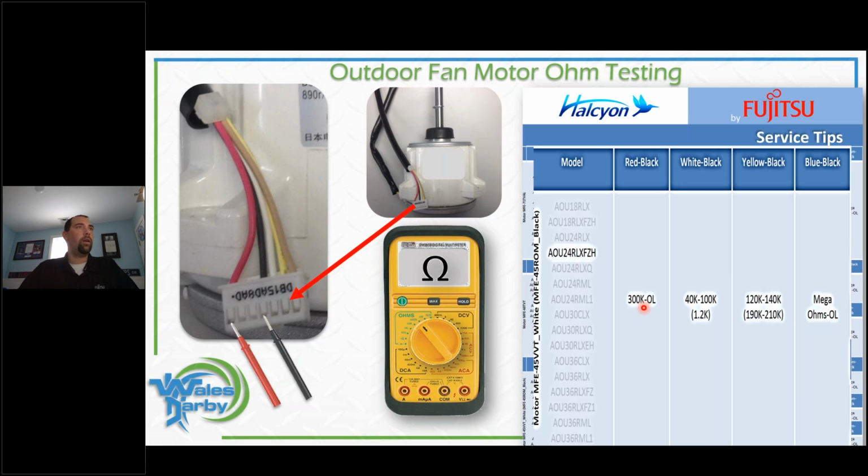I see, Ben, you had down there, you have an auto meter, right? So it's auto ranging. So auto ranging can be good. It might not be good. It really depends on the multimeter and you understanding the readings you're getting. And that's where I say, if I have a selectable meter like you see here on the screen, I have to actually dial in at a range a little bit higher than the reading I'm expecting.